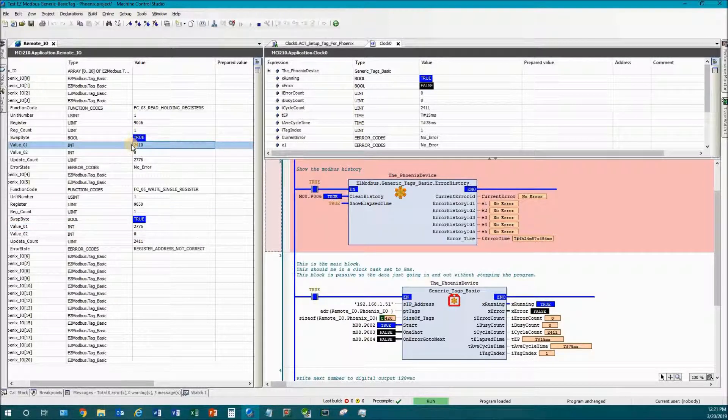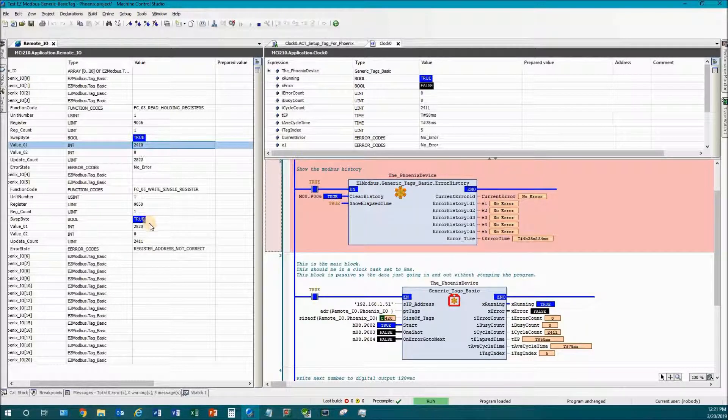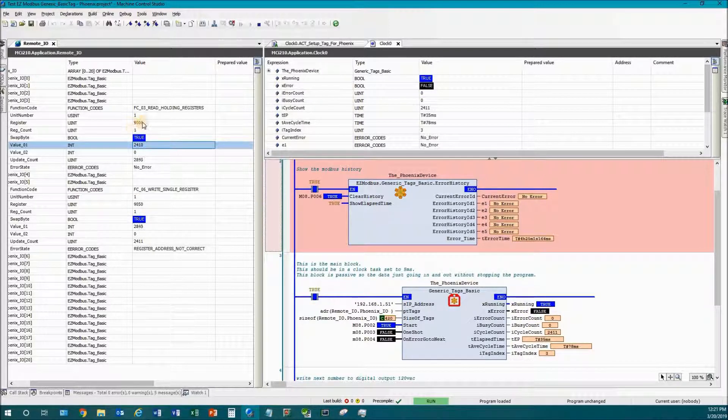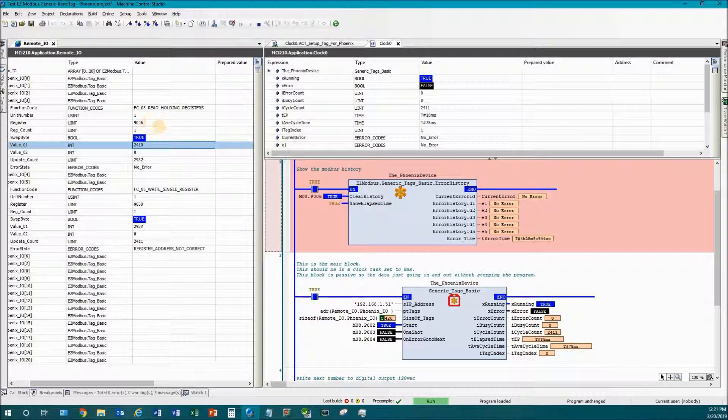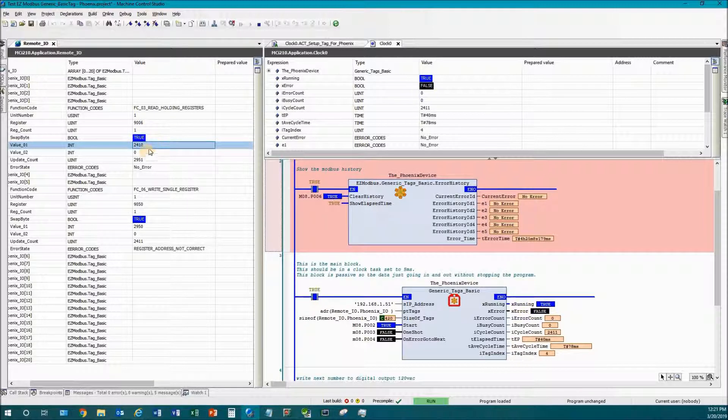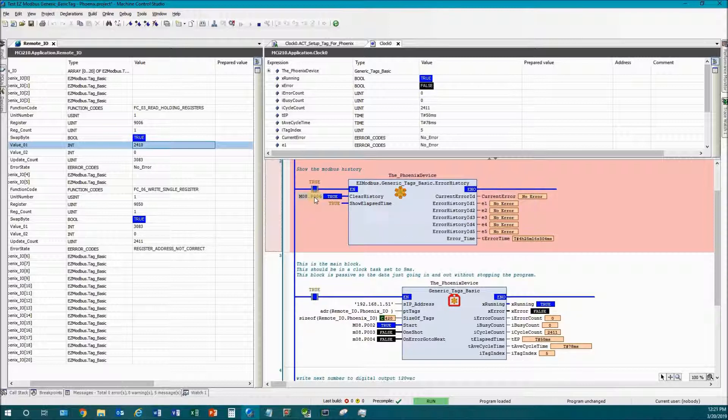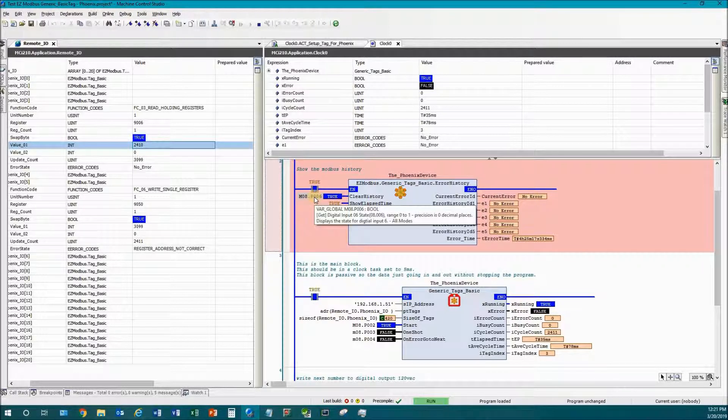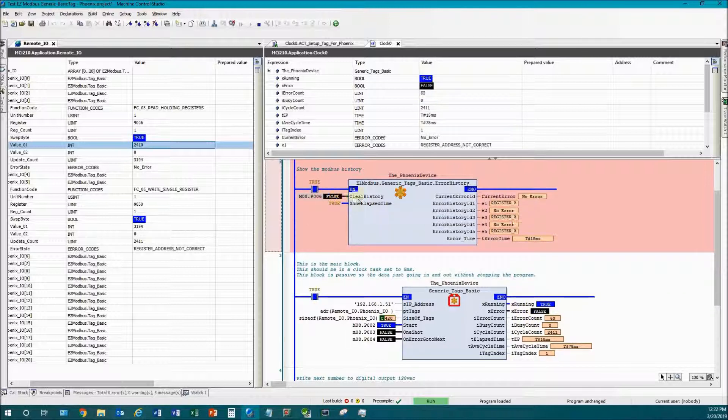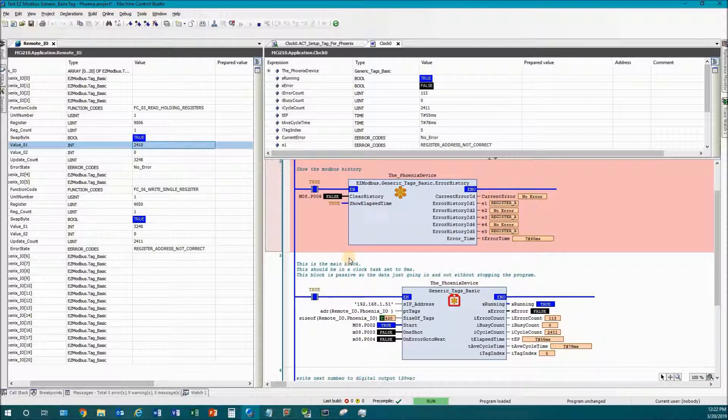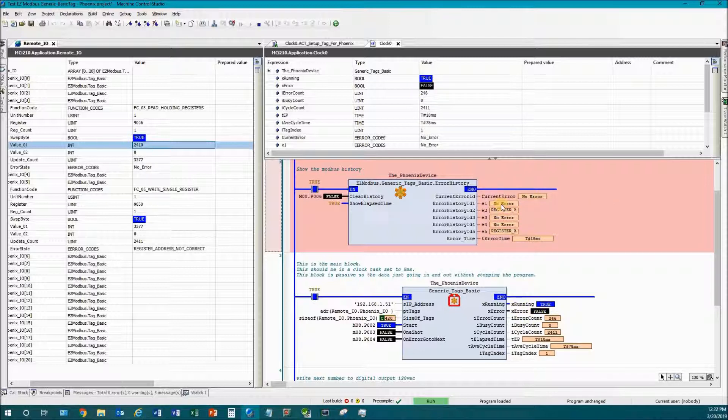Now we're still trying to write these values here, but you notice because I'm not writing to the same register this value here is not updating anymore. In other words, because I'm not writing it to 9006, I'm still reading it, it's just the value is not changing. This says there's no errors over here but that's because this input six is on. I turn that off and every time it goes and reads past this particular tag it's getting this error history.